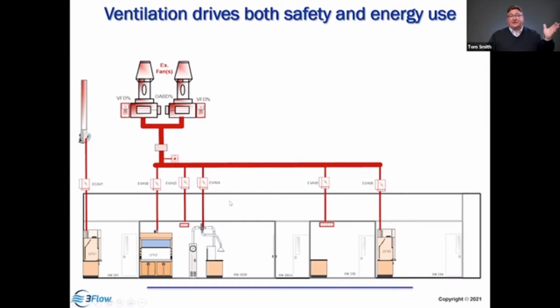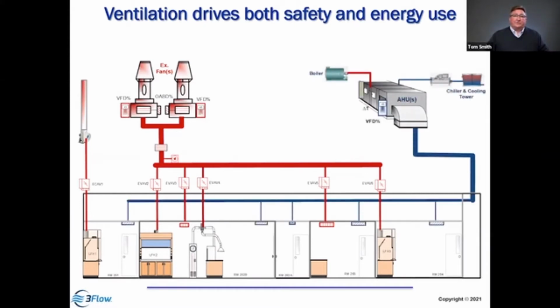So we're exhausting air out of the space, removing the contaminants. But because we're pulling air out, we have to bring air back in to supply makeup air. And we have to control that distribution as well. So now we're starting to get pretty complicated. We've got an arrangement of systems that are essentially independent, the exhaust and supply, but they're not mutually exclusive. They need to work together in order to achieve the objectives of a safe and productive space.